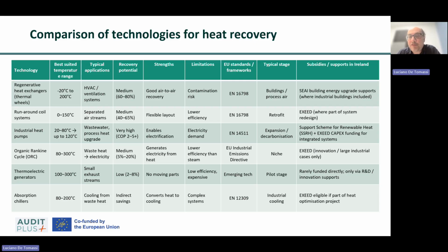Regenerative heat exchangers, often referred to as thermal wheels, are widely used in ventilation and air handling systems operating at temperatures ranging from below freezing to approximately 200 Celsius degrees. A thermal wheel works by rotating a heat-absorbing matrix between the warm exhaust air stream and the cooler incoming air stream, transferring stored heat from the exhaust air to the fresh air supply.